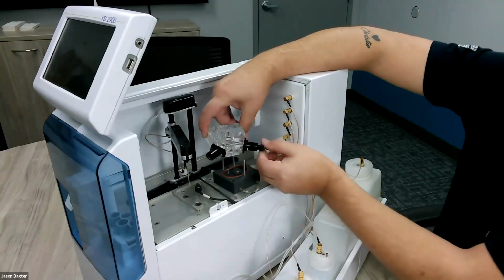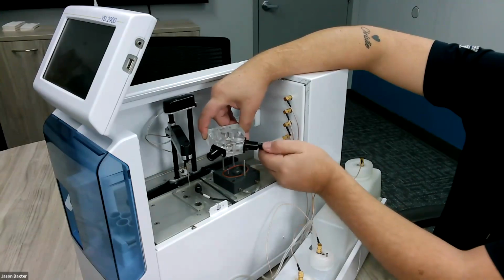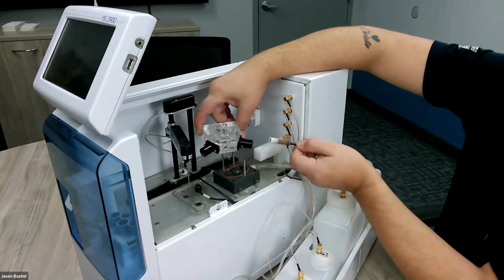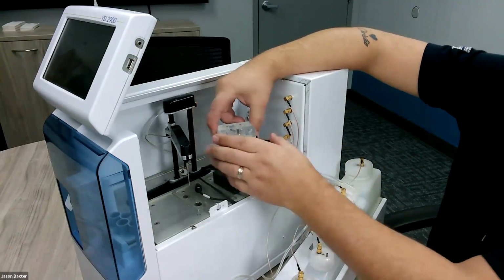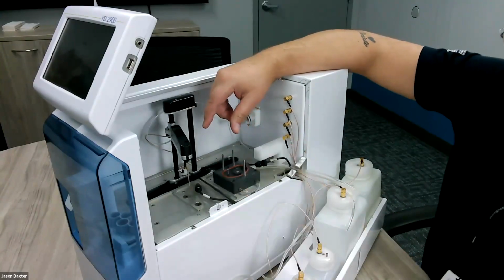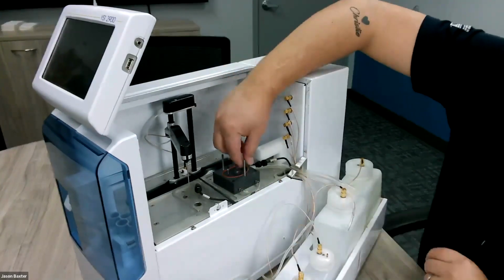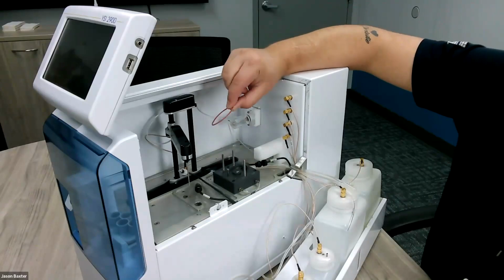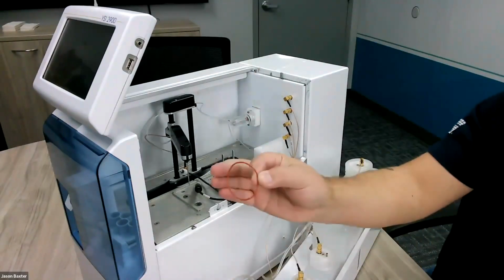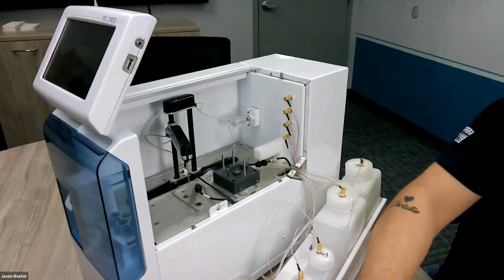So unscrew the probes, just simply unscrew. Once you have the nut unscrewed, you can pull the probe out. Set this sample chamber off to the side. Remove the small O-ring that goes between the sample chamber and the waste chamber. This O-ring can be discarded.